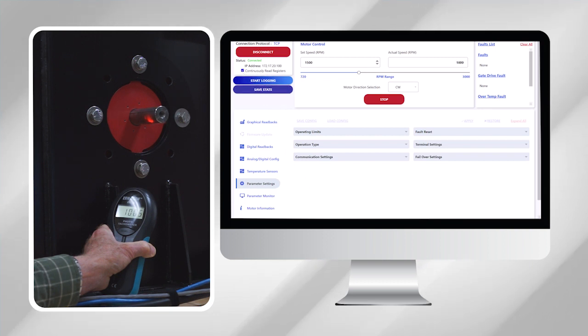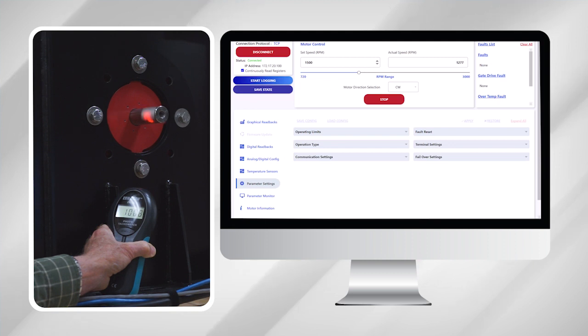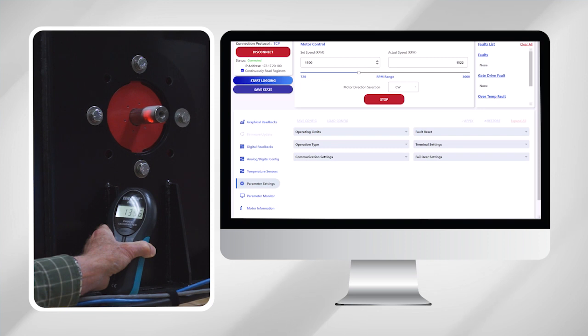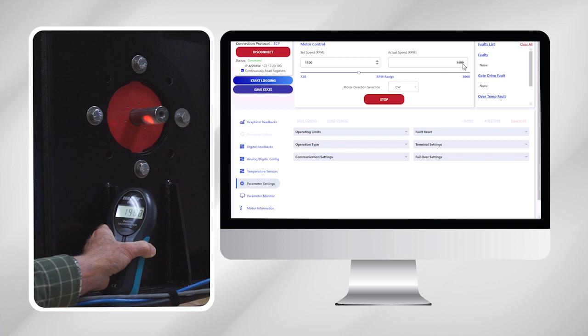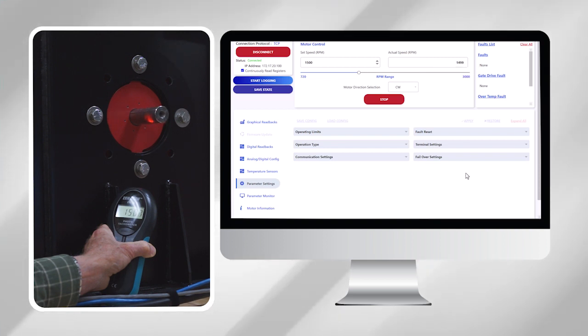I restore communication, speeding up. And now we're back to 1500 and the tachometer and the laptop agrees with it. You can see in the upper right hand corner of the laptop, it's the speed we expected it to be. So this is a test and a demonstration of the failover mode.